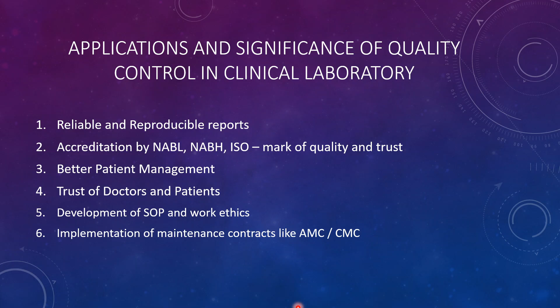But different quality control programs are there. We talked about quality control, and now there are different types of quality control programs. One is internal quality control and the other is external quality control. What is internal quality control? Internal quality control basically is the daily run of controls. These controls have known values and are run in the lab to check the quality of tests via the Westgard rules, something which we have just seen. So all the controls which I talked about, I was referring to the internal quality control program, where you daily run control values and see whether they follow the Westgard rules or not.